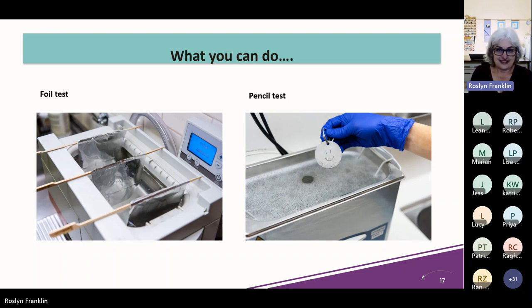Add your detergent and degas again. Now that does take time, so a good time to do a foil test is just before you're going to change the solution. If you're a busy dental practice, that might be mid-morning or at lunchtime, because that cleaner is more like a bath, and that water and detergent needs to be changed quite regularly as soon as it becomes dirty, otherwise it's not going to be cleaning as effectively.